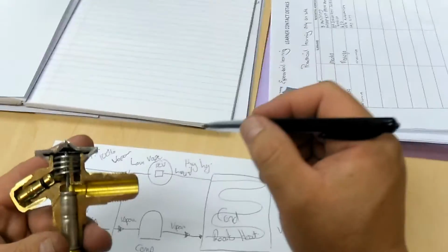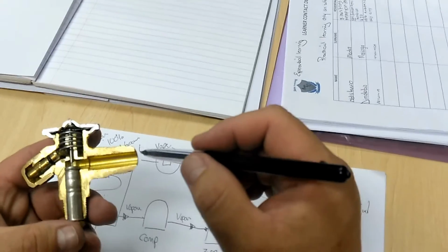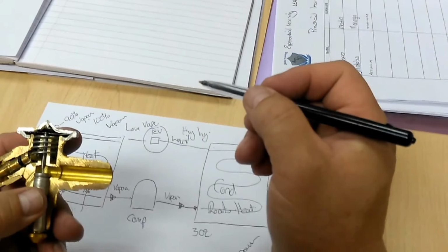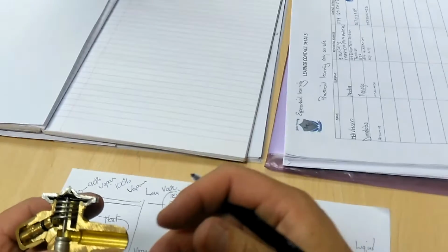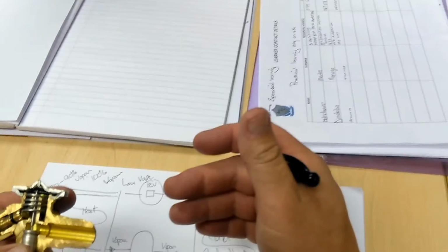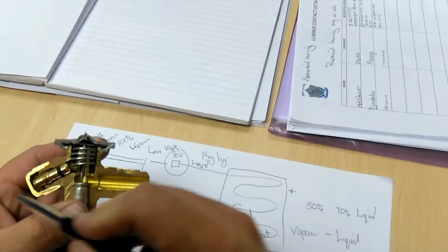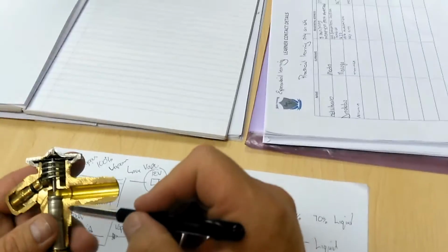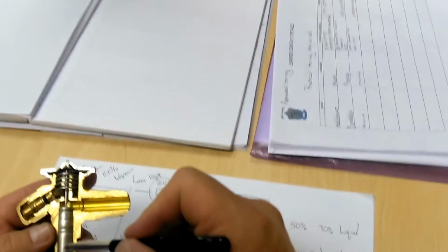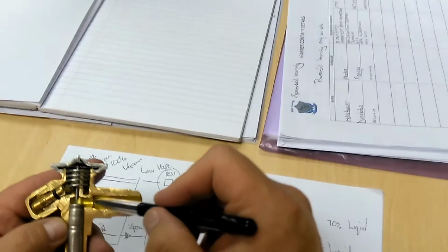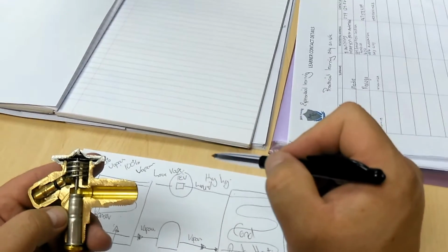The terminology used in this case: by turning in the spindle all the way, we're starving the evaporator, meaning that there is little or no refrigerant entering the evaporator. Then, by turning the spindle all the way out, we're flooding the evaporator. This means we have too much liquid refrigerant entering the system and bypassing the proper sequence that needs to take place.